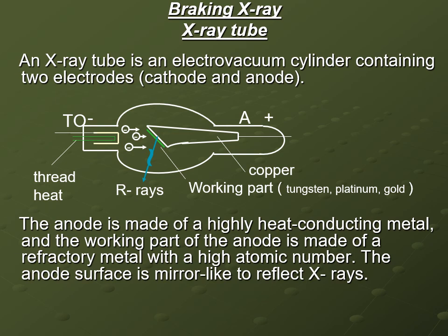That is, a sufficiently low pressure in the X-ray tube should be maintained. In addition, this tube contains a cathode, designated here by the letter K, and the anode is marked with the letter A. The cathode is negatively charged, the anode is positively charged.